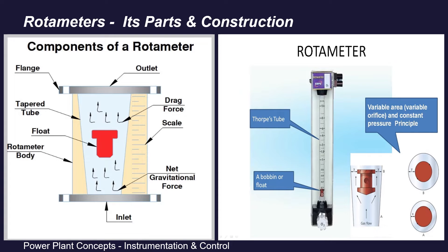Coming to its different elements, basically a rotameter has three main parts. First is a uniformly tapered flow tube. Second is a float that rises up or moves down depending upon the pressure exerted by the fluid entering the rotameter. Third is a measurement scale — a calibrated scale in which the float position is calibrated to display the corresponding volumetric flow rate reading.